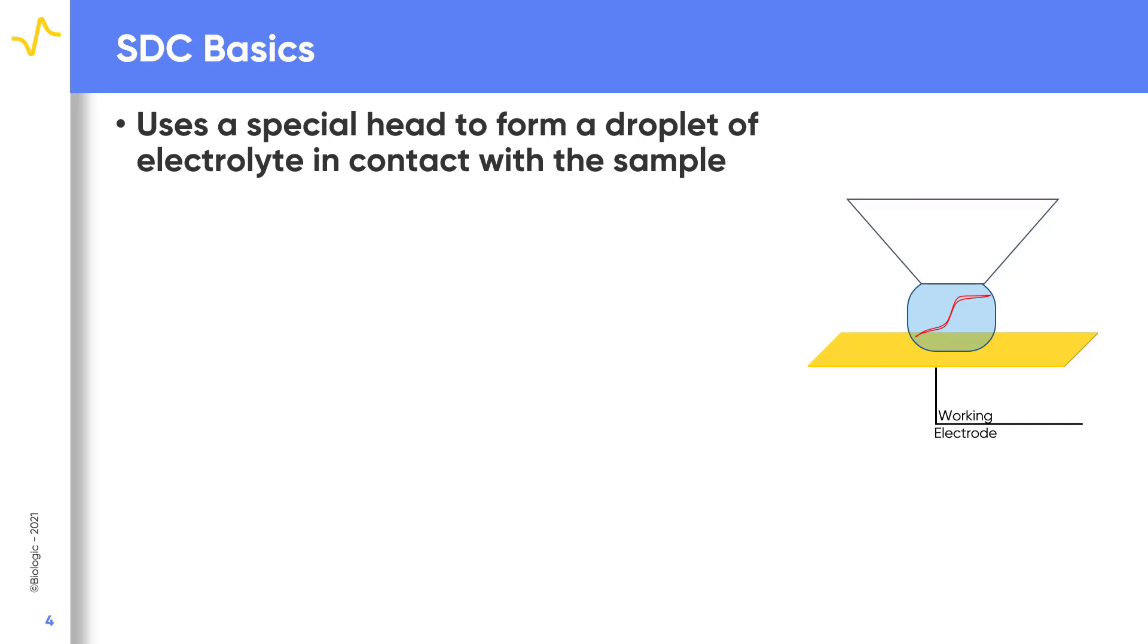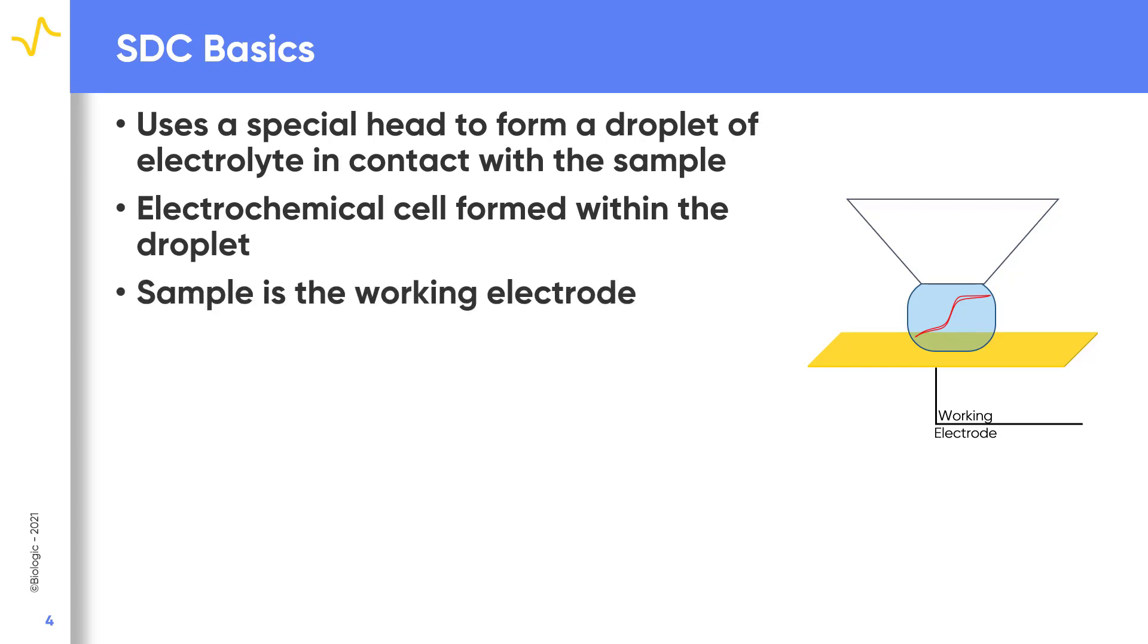A special head is used to allow this droplet of electrolyte to form with the sample. The electrochemical cell is then formed within the droplet. The sample acts as the working electrode which has an area equal to the droplet contact. The counter and reference electrodes are then contained within the head.